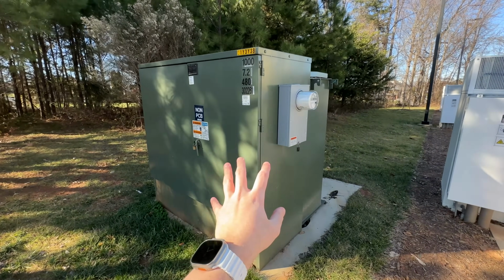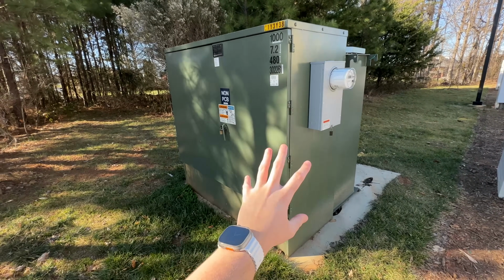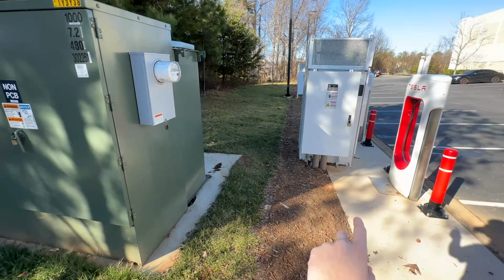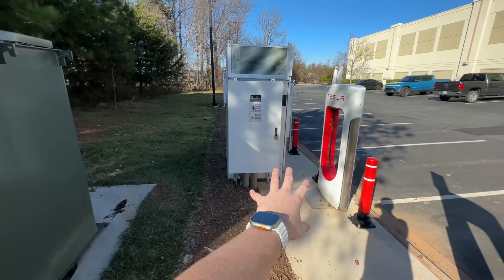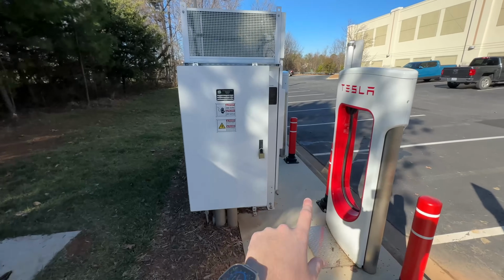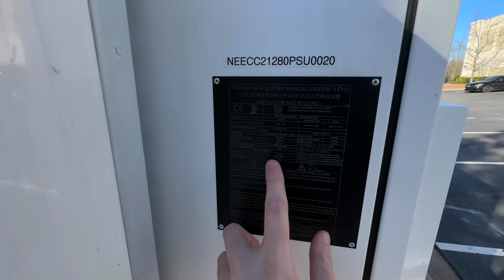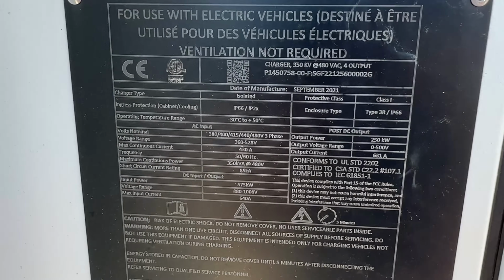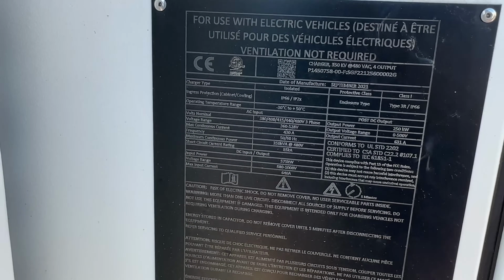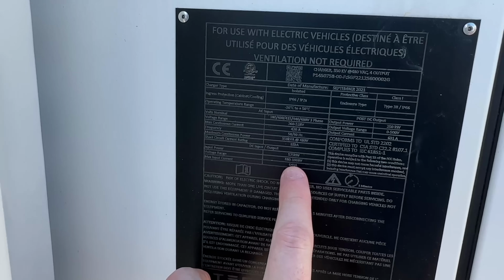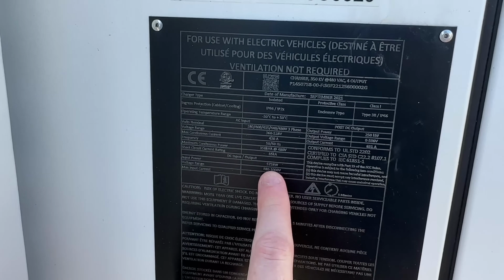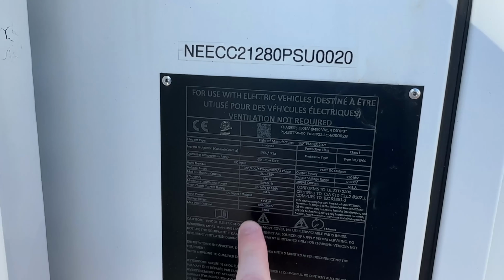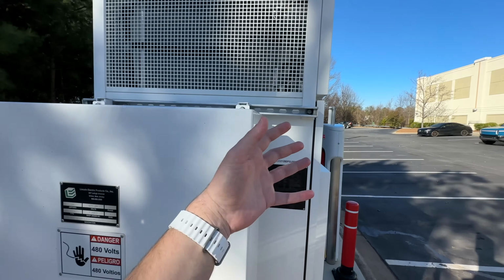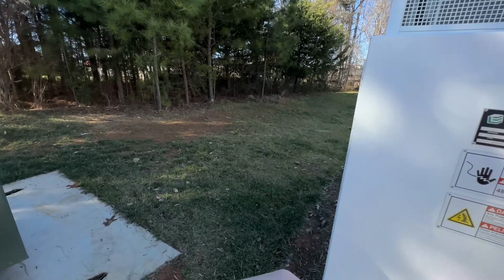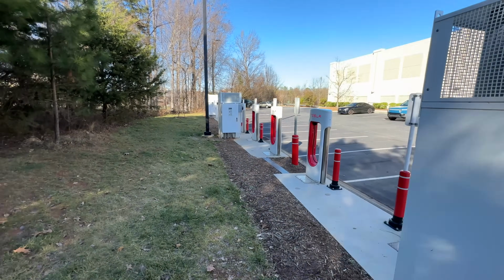As I mentioned, we have the utility transformer here. Directly out of this utility transformer, you have two 4-inch conduits going to each one of these prefabricated supercharger units. The reason for that is these cabinets are actually only about 350 kilowatts—you can see they're 350 kVA, which with the near 1.0 power factor is essentially 350 kilowatts roughly. But there's also a DC bus, so these can actually take in and out up to 575 kilowatts per cabinet. You'd actually have to have two cabinets feeding one cabinet in order to have that 575 kilowatt input.